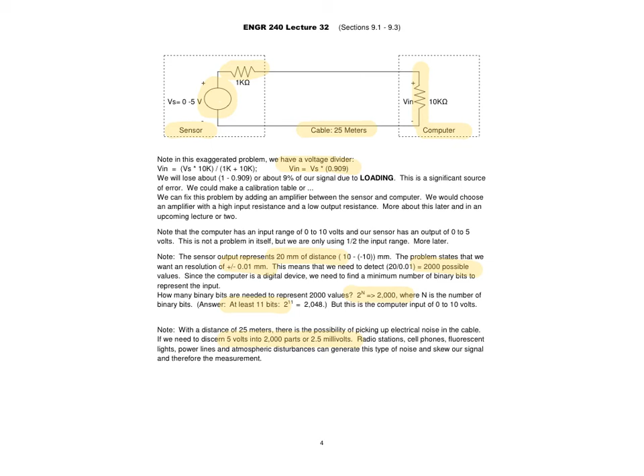Looking at it another way, if we took this 0 to 5 volts and divided it into 2,000 parts, it means that we have to have 2.5 millivolts of resolution in order to get that accuracy. This 2.5 millivolts has to be protected fairly carefully as it makes its trip from the sensor to the computer. Everything from radio stations, cell phones, power lines, everything can add their own signal into our signal. These undesired signals are called noise. We need to deal with noise.